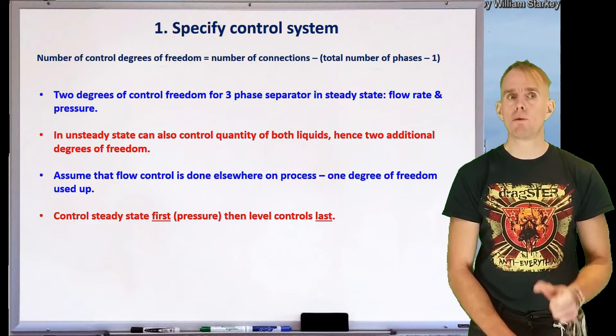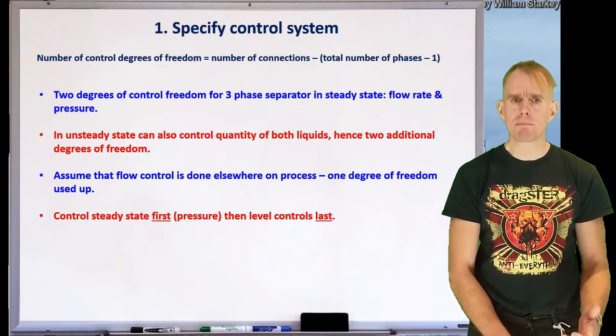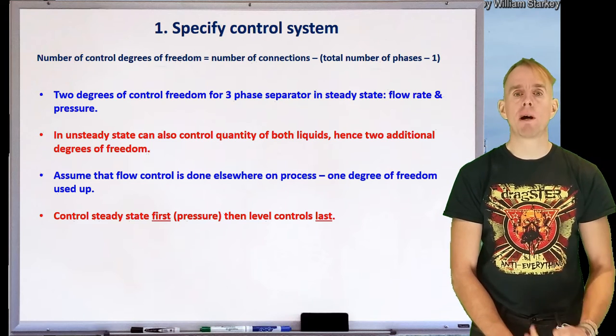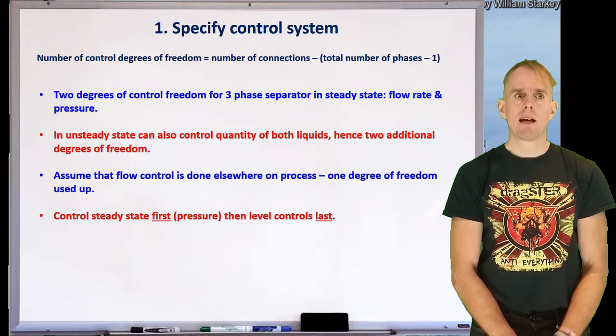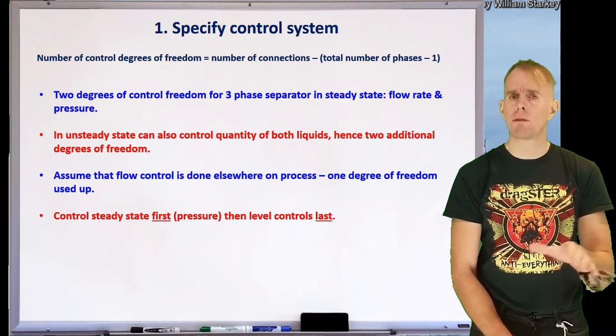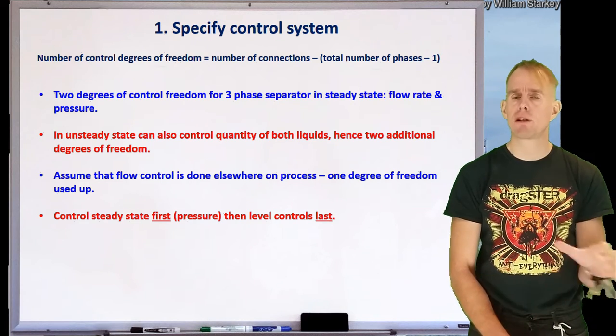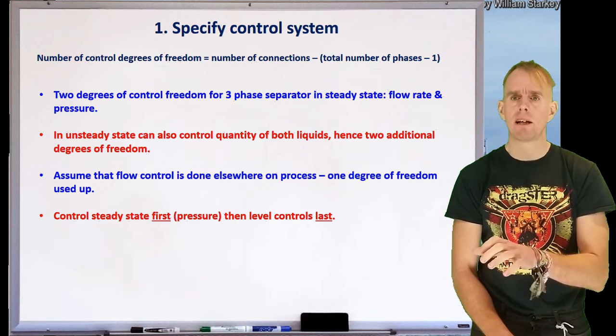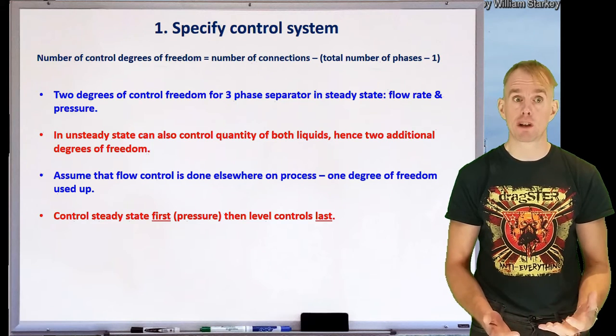That leaves us with two degrees of control freedom for steady state: flow rate and pressure. We haven't got temperature because there's no way of heating or cooling the contents of the separator. And if we consider flow rate, we may have already controlled that elsewhere on plant, because for the major process flow through a plant you only control it in one place — otherwise multiple controllers on the same line end up fighting each other and the control system simply won't work.